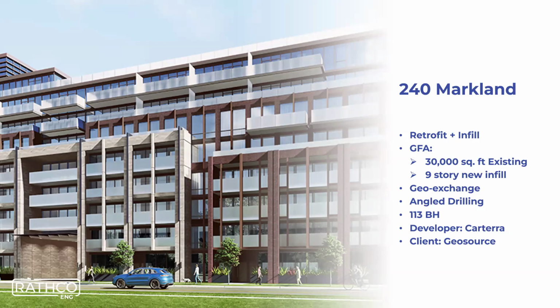Well, GeoSource has these really cool drill rigs that can angle the mast. So we put them in the parking lot beside the building and angled the mast at two different angles, a 15 and a 25 degree angle. Then we did some really fancy geometry and fanned that out, creating a sine wave of boreholes underneath the existing building by drilling beside it. This allowed us to put enough GeoExchange bore field underneath the existing building, plus enough capacity for them to build a sister building beside it that was twice the size of the first one.